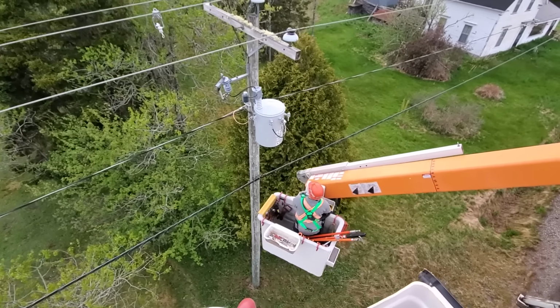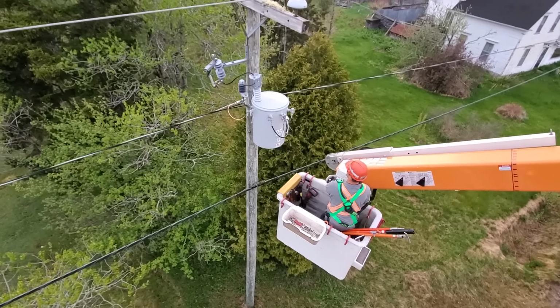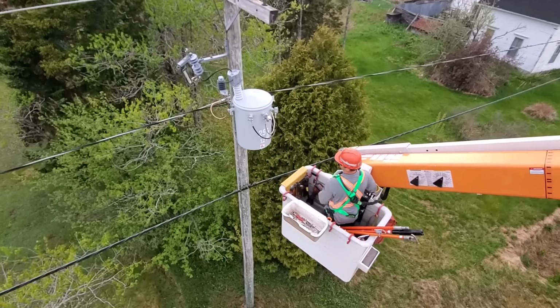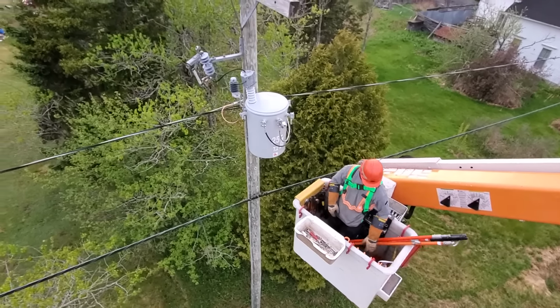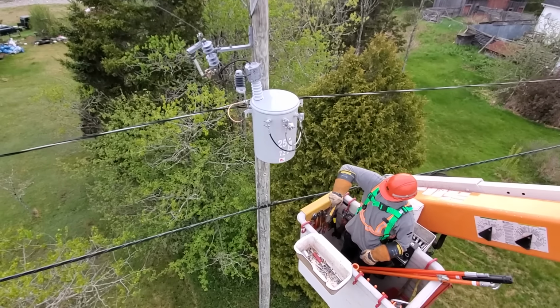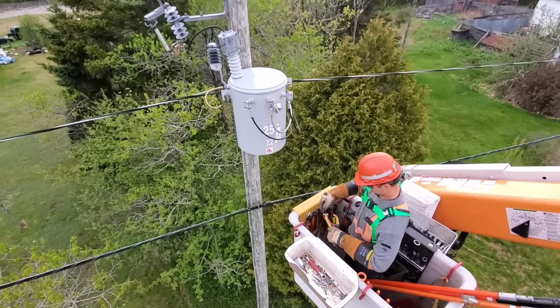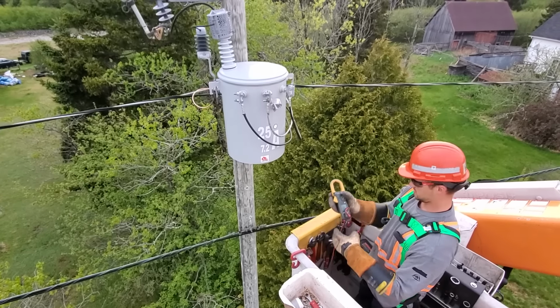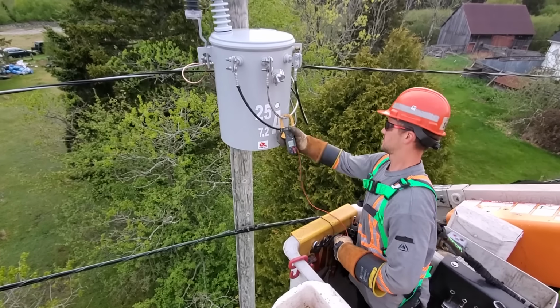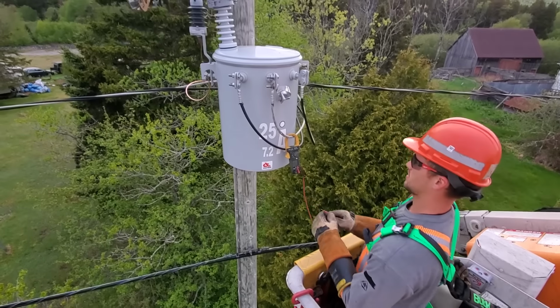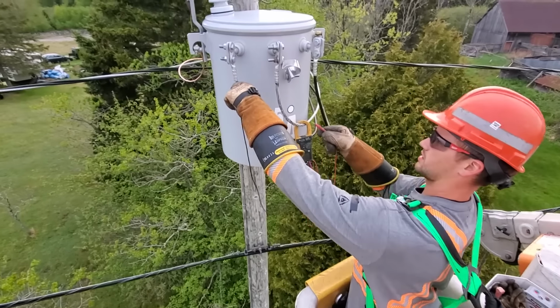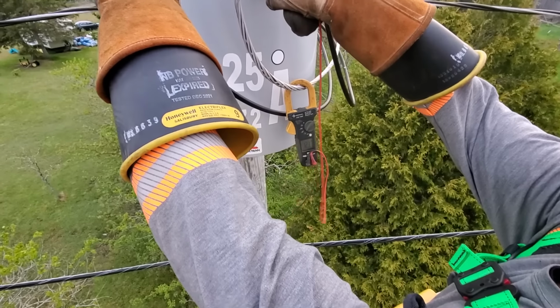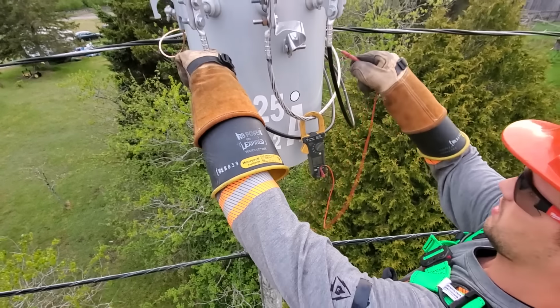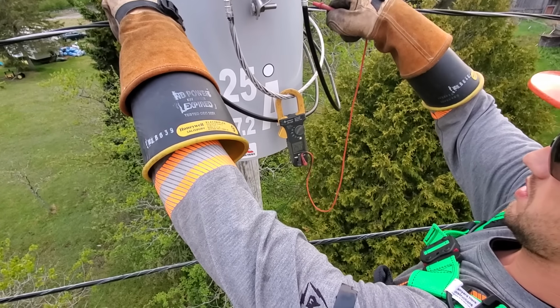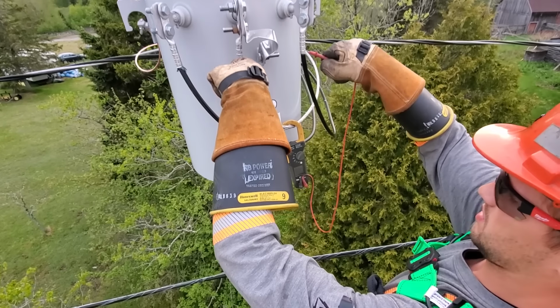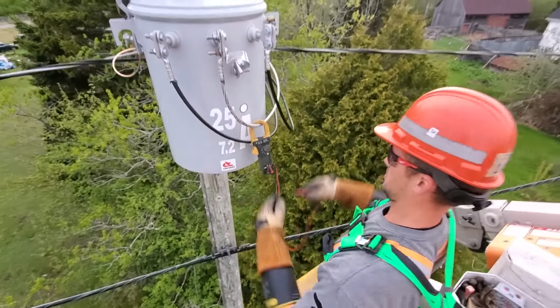And one last step he's going to be doing is a voltage check. I suspect we'll see something probably along the lines of 123, 124 volts from each hot. And then you always want to check across both hots to make sure you do have your 240 in case there was a manufacturer's defect in the windings of the transformer, which is extremely rare. So going from a hot to a neutral, we've got 123.8, hot to hot, we've got 247.5, and our other hot, we've got 123.7.